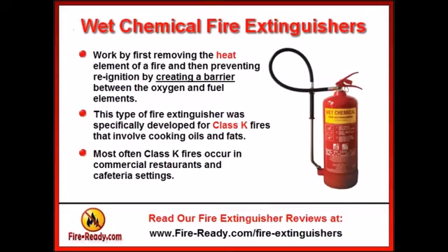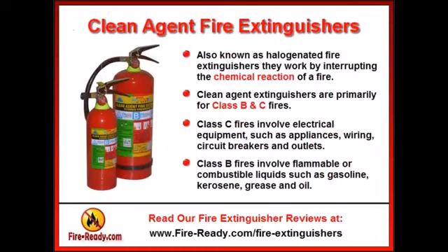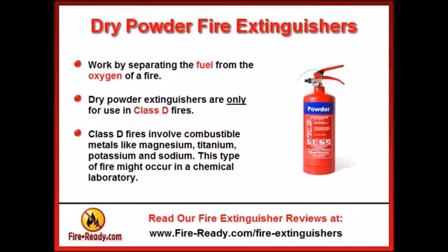This type of fire extinguisher was specifically developed for Class K fires that involve cooking oils and fats. Most often, these Class K fires occur in commercial restaurants and cafeteria settings. Clean agent or halogenated fire extinguishers work by interrupting the chemical reaction of a fire. Clean agent extinguishers are primarily for Class B combustible liquid fires and Class C electrical fires. And finally, dry powder fire extinguishers work by separating the fuel from the oxygen of a fire. These are only for use in Class D fires that involve combustible metals like magnesium, titanium, potassium, and sodium.